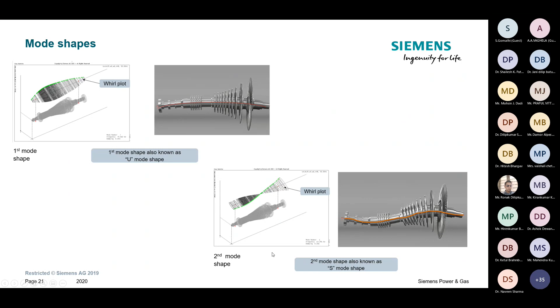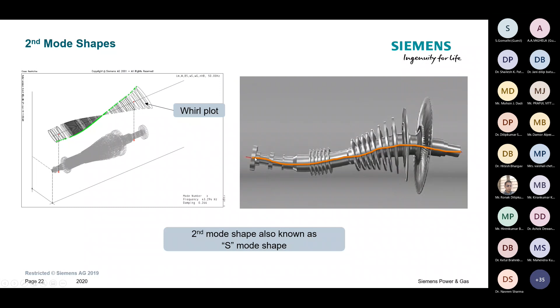And as I said earlier, here whirling of the motion will come. If this shaft is rotated at the first critical speed, which is around 19 hertz, then it obtains this shape. That means the whirling happens at all sections, but at the center it is maximum and at the bearing it is minimum. That is the first mode. Then the second mode, the rotor obtains this S kind of shape, so we call it S shape also. Here you can see at the center, if you put a probe, you get a vibration of 0. But if you have a probe at the bearings, you will have the highest vibration, because the highest whirling is happening over there, right? So that is called the S mode. This is an exaggerated view, and this is the real one. When the shaft is vibrating, it will obtain these shapes, right? So you will have a change in the phase angle and all those things that you can come to know.